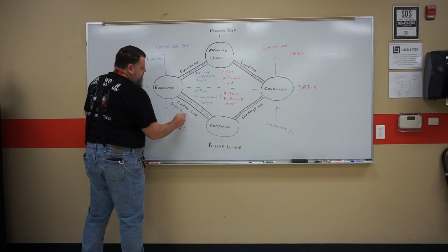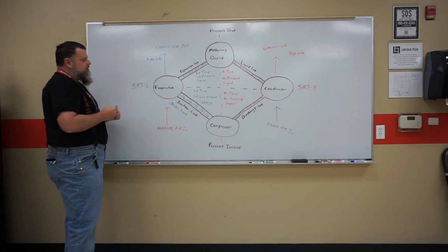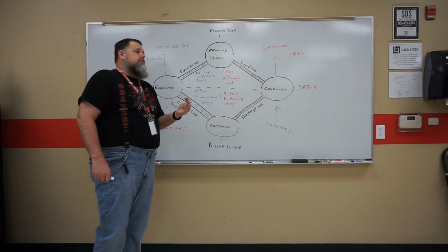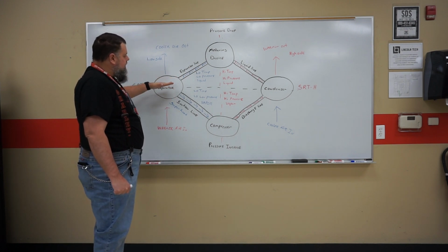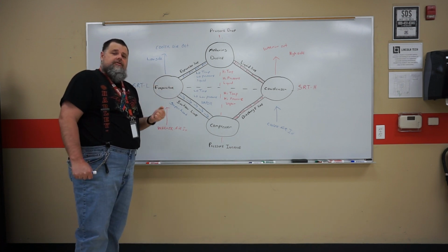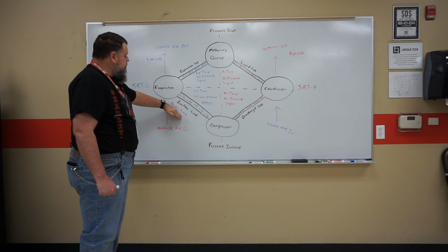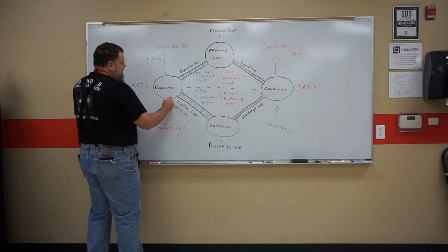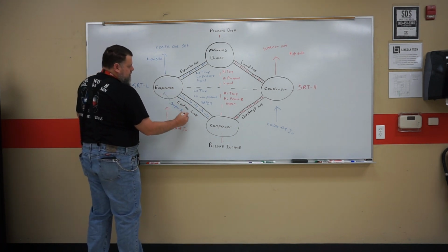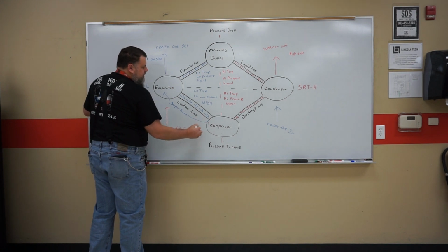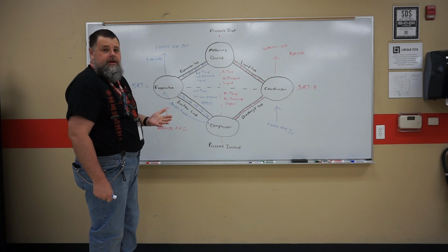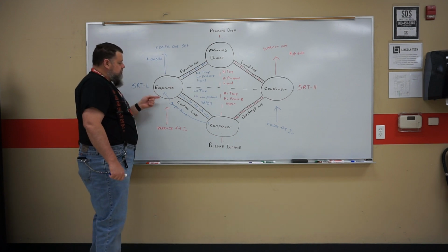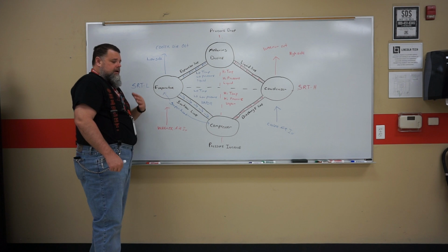Well, when you talk about superheat, superheat is always a vapor. Basically what that means is once this liquid has boiled off, any more heat we add to it just raises the temperature and doesn't change the state. So we have superheat, and you pick up superheat all through here, all the way into the compressor. That's why we have that line insulated so we don't pick up excess superheat going through an attic. So superheat is on this side right here.